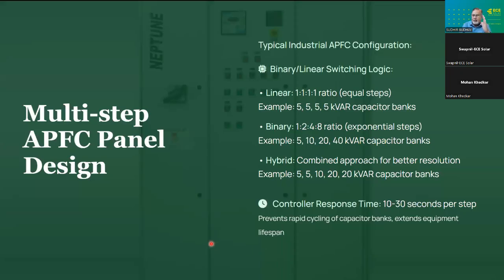So when we want to select a relay, we have 3, 4 options in the market. One is we can go for linear logic, which is 1:1:1. So I have similar capacitors placed, 5 kVAR, 5 kVAR, 5 kVAR, 5 kVAR. This is an example. So you keep switching on in the same linear fashion. Second is exponential steps, binary 1, 2, 4, 8. So we put capacitors 5, 10, 20, 40 kVAR.